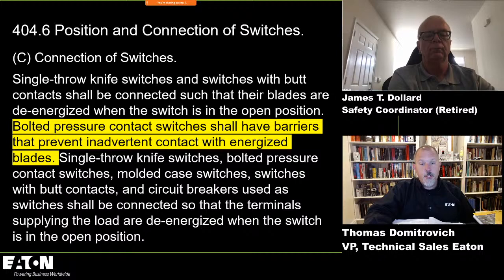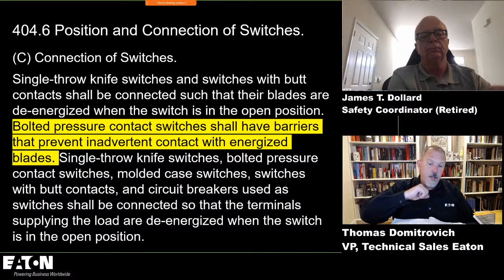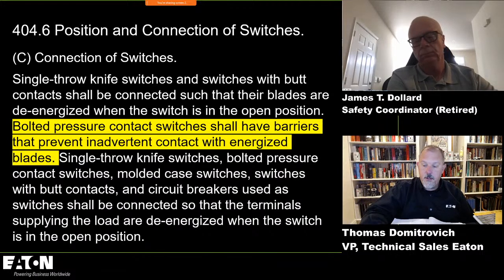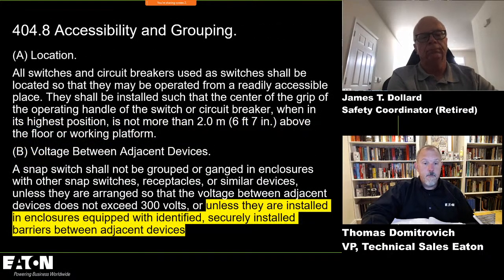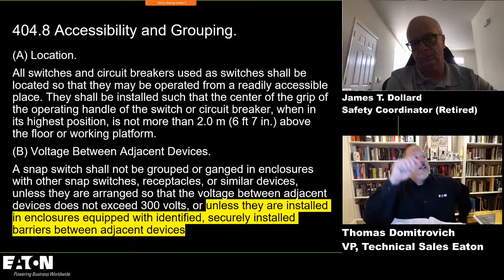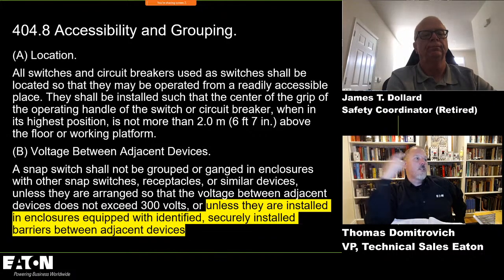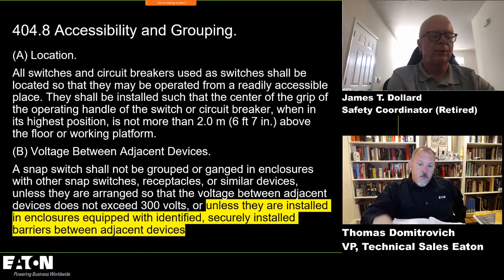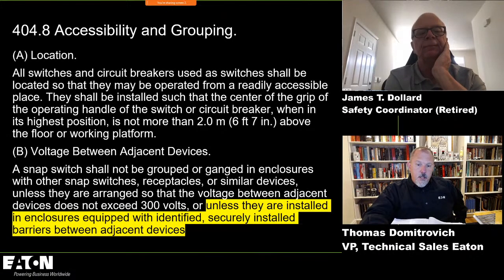404.6. Bolted pressure contact switches shall have barriers that prevent inadvertent contact with energized blades. Single throw knife switches, etc. So you'll always see on those disconnects and whatnot that plastic cover that is supposed to help prevent coming in contact with energized parts. And those plastic covers do a poor job of preventing inadvertent contact. Yeah, and probably primarily because of all the space that's around there. It's not an IP2 or IP7 or whatever that standard is. Those aren't finger-safe solutions. Yeah, I'm not familiar with the numbers there. Yeah, so unless they're installed in an enclosure.